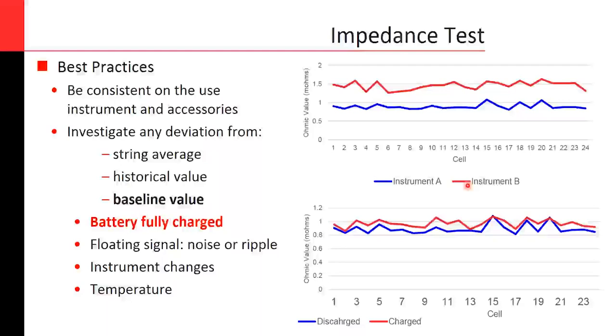And this, I have it highlighted because it is an important value to calculate, to obtain. It's something that will be dependent on each string, on each cell. And the way to calculate this is from some averaging of good values, which you need to establish or determine when doing your measurements. There's software that can help you to do that, and will establish the baseline value from the measurements that you have been performing.